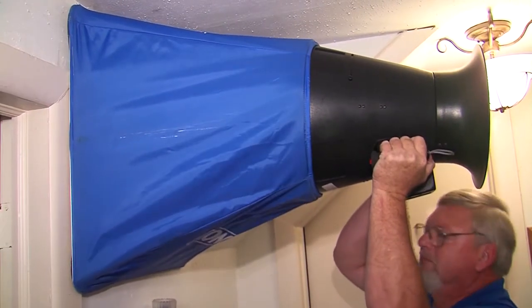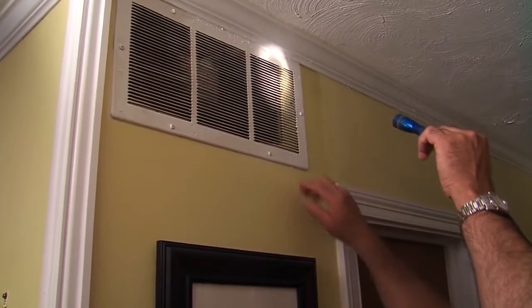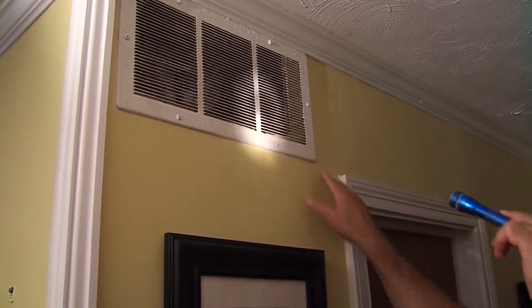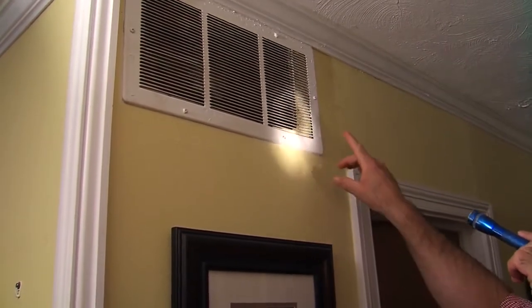There's supply air, where the air comes from an air handler or furnace and gets blown into the rooms, and then you have return air, where the air is being pulled from the rooms and going into the return side of the equipment. What we run into oftentimes is that the supply might not be that bad, but there's completely inadequate return air. There might be one central return in the house, when really, in order to get exchanges of air as often as you should, there should be returns in different rooms.